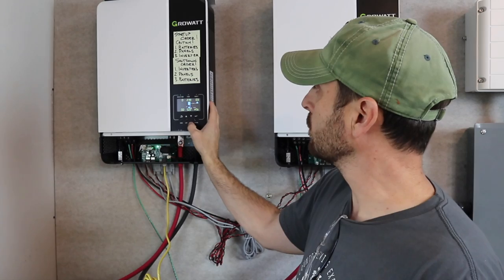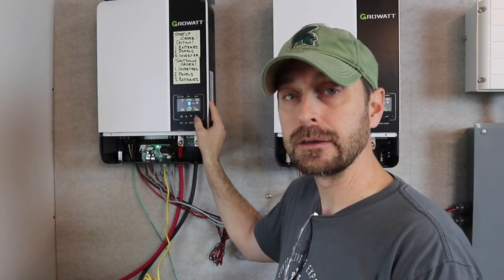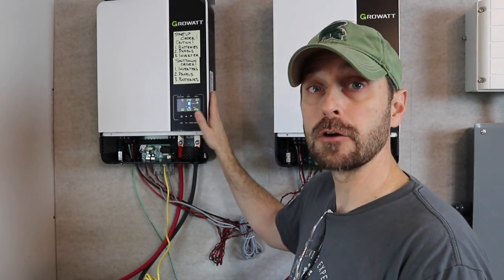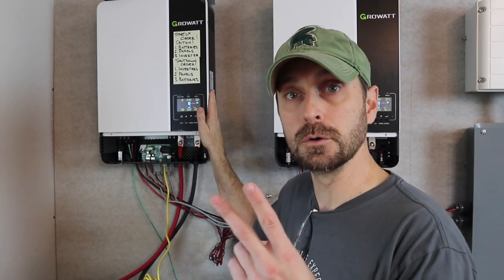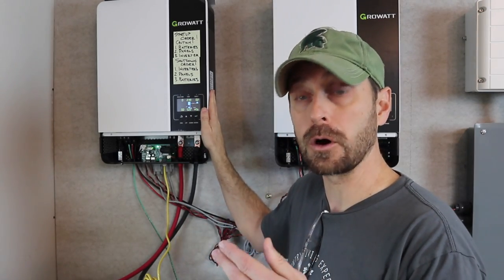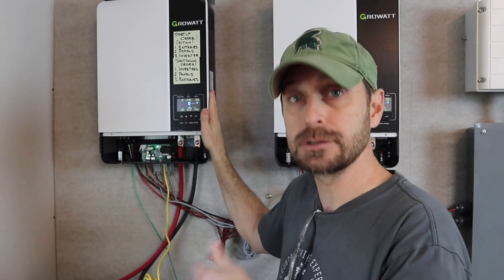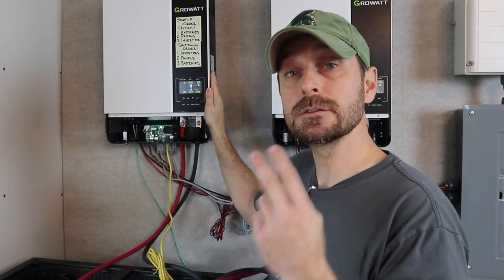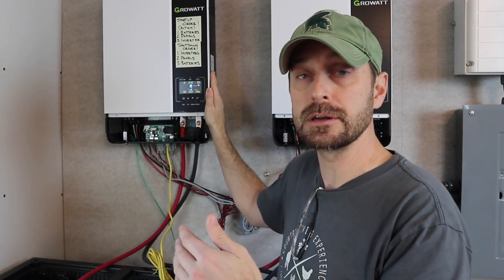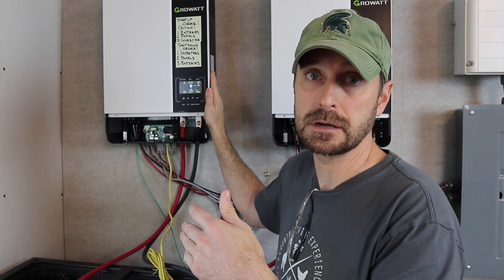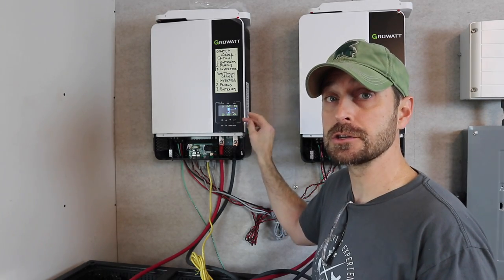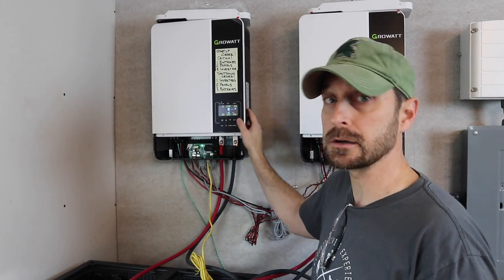So I am gonna go into function 5 and I'm gonna change this from user setting 2, which is what I had it set before because I didn't have my communication cable set up. User setting 2 is used for lithium batteries when you don't have that communication set up. But now we can go in there and change it to lithium and they'll start talking to one another.